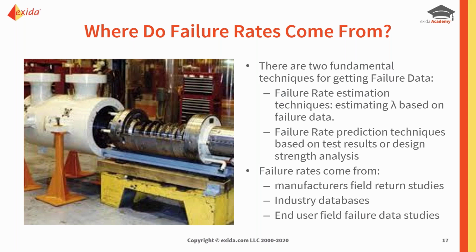The other thing is time. A lot of manufacturers will assume that as soon as it's left the factory, it's in service, which of course we know that's not necessarily going to be the case, because they could be going into storage as spares. They could be waiting for commissioning activity to be available at site, which could be 12 to 18 months after shipment. Who knows? So that's another thing.